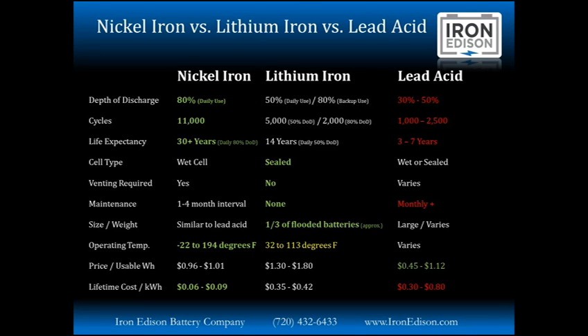This number is the purchase price. Nickel iron batteries are roughly $1 per usable watt hour of capacity. Now remember the word usable, that's factoring in the supported depth of discharge. Compared to lead acid, well, yes, lead acid is a cheap battery, and that's probably the only benefit to lead acid batteries. But when you look at the lifetime cost per kilowatt hour, that number is the purchase price divided by the total kilowatt hours of capacity that battery can expect to deliver over its lifetime.